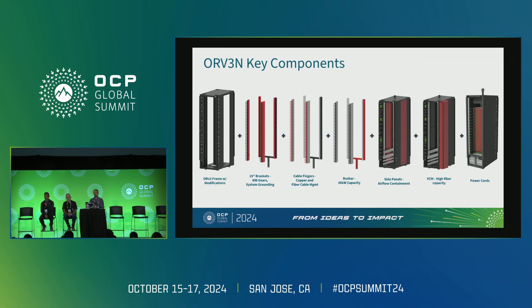Here are the key components of the ORV3N rack, starting from left to right. We basically took the ORv3 frame and bolted on four 21-inch to 19-inch adaptive brackets. On top of that, we added one OU pitch cable fingers for maintaining fibers and copper cables. In the rear, we added a 48-volt DC offset bus bar to address some of the serviceability concerns. We added side panels for air flow containment. For certain deployments, we introduced an accessory kit called the VCM — vertical cable managers — to support higher fiber capacities. And we developed custom power cords for each network gear.